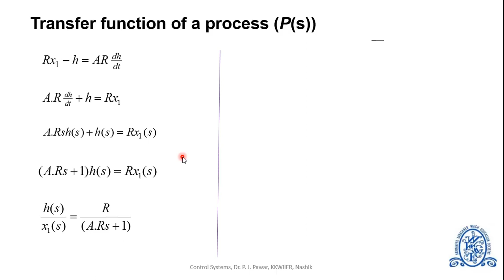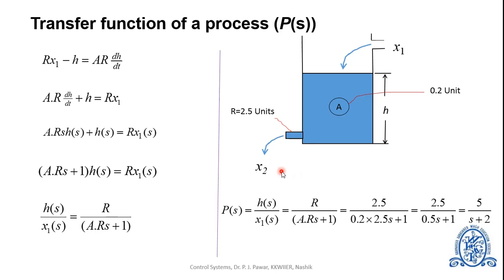Now to study the system output for a given flow process using different control actions, assume constant values like area of the tank as 0.2 unit and the resistance offered by the orifice as 2.5 units. Now if I substitute these values of A and R in this particular equation of the transfer function, substituting R is equal to 2.5, A is equal to 0.2, we can obtain the transfer function of the process as 5 upon s plus 2. So we obtain the transfer function of a controller and the transfer function of a process for our flow process problem.